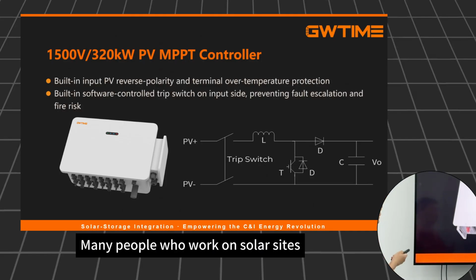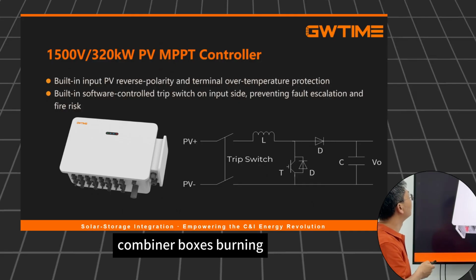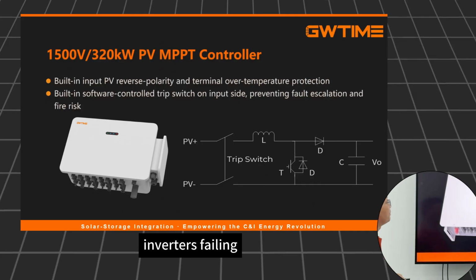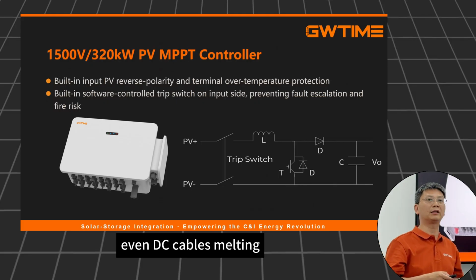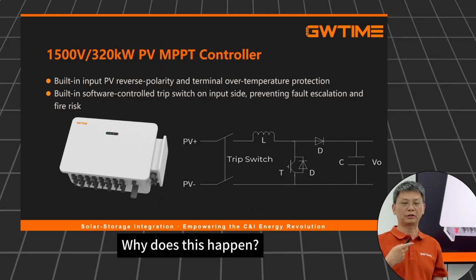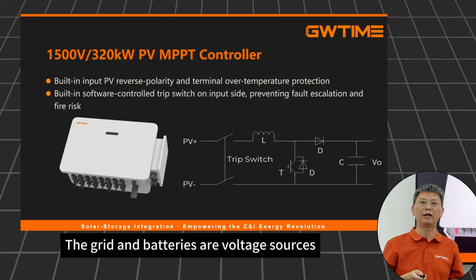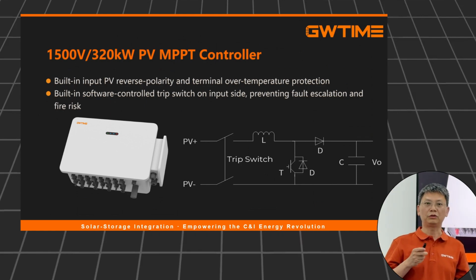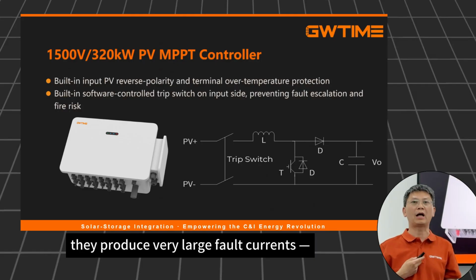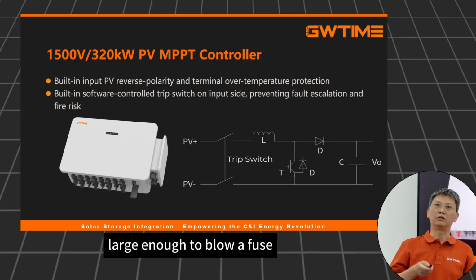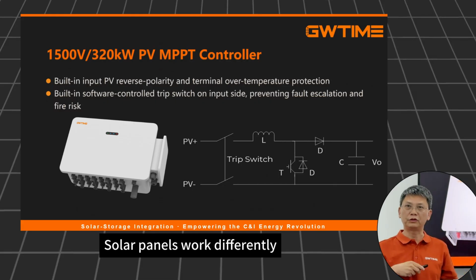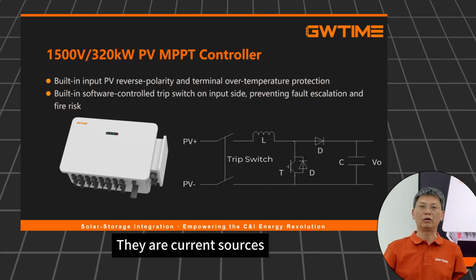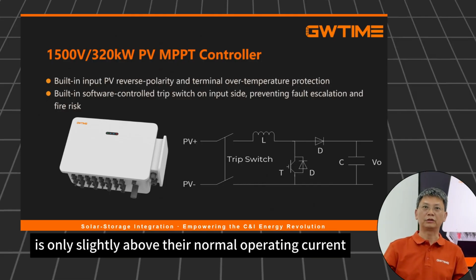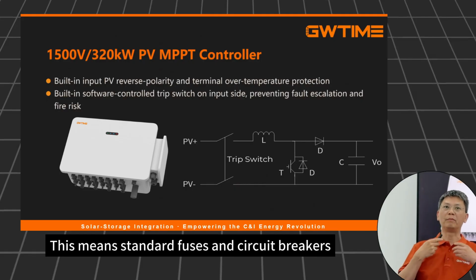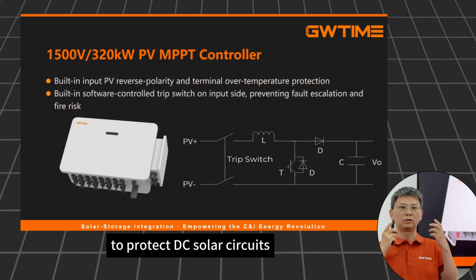Many people who work on solar sites have seen fires: combiner boxes burning, inverters failing, hybrid units catching fire, even DC cables melting. Why does this happen? The grid and batteries are voltage sources. When there is a short circuit, they produce very large fault currents, large enough to blow a fuse or trip a breaker. Solar panels work differently. They are current sources. Their short circuit current is only slightly above their normal operating current. This means standard fuses and circuit breakers do not work well to protect DC solar circuits.